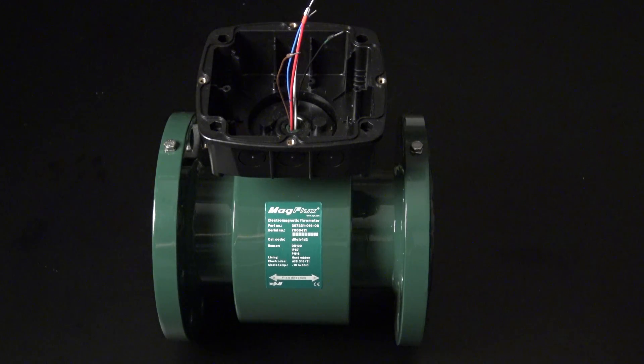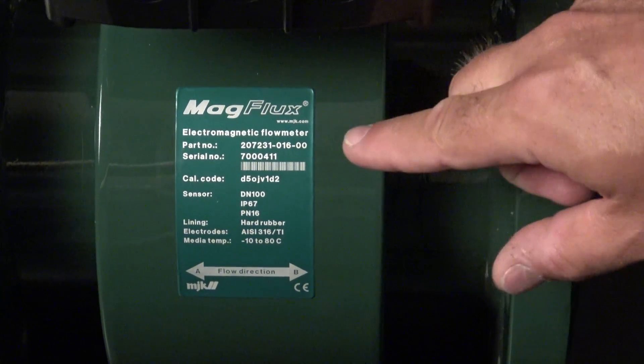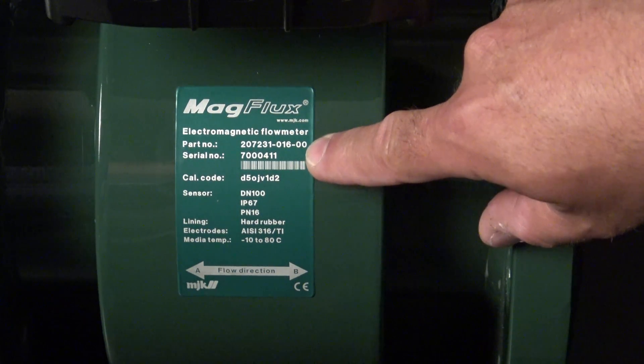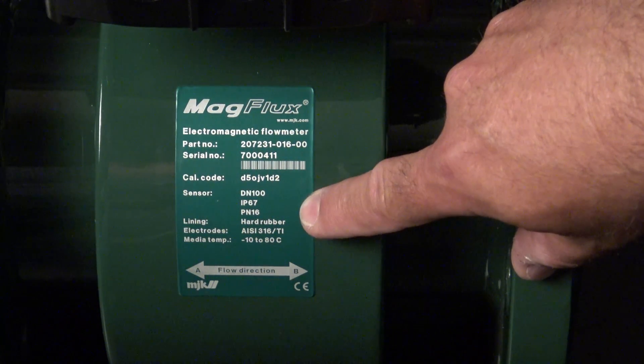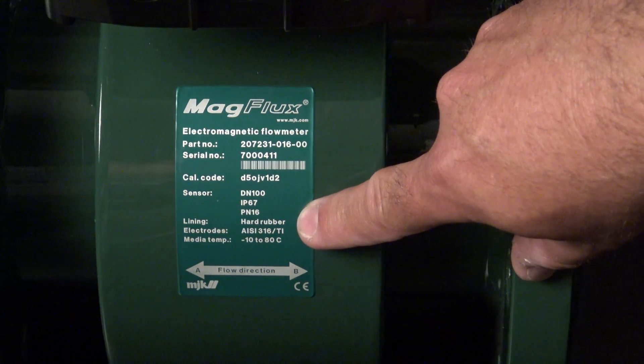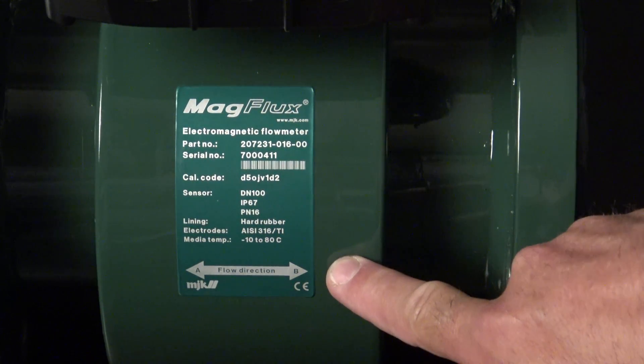Inside the sensor tube we have the electrodes. The coils generate the electromagnetic field which we use to measure the flow. On the side of the sensor we have the sticker on which you can see the part number, the sensor serial number, and the calibration code we need when we install the converter. We can see the DN size, IP class, and pressure class. Furthermore we can see the liner type and the flow direction of the sensor, which we also need when we install the converter.